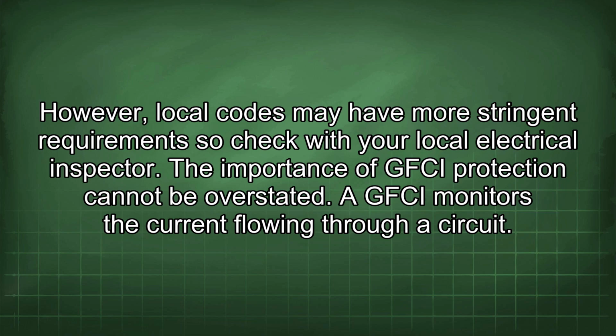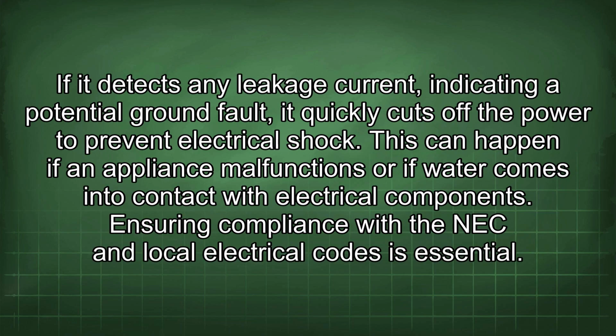The importance of GFCI protection cannot be overstated. A GFCI monitors the current flowing through a circuit. If it detects any leakage current indicating a potential ground fault, it quickly cuts off the power to prevent electrical shock. This can happen if an appliance malfunctions or if water comes into contact with electrical components.